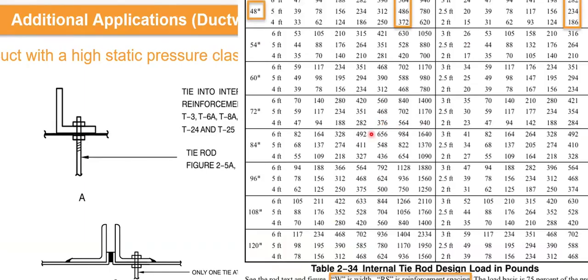This is a snippet that I included for a 48-inch wide duct. If you wanted to meet the 6-inch pressure rating, for a spacing of 4 feet for reinforcement, you need a tie rod that could withstand up to 372 pounds of force or load. If you wanted to increase that spacing to 6 feet, you need a much bigger tie rod that can withstand 564 pounds. Once you begin to have all of these every 6 feet, you're beginning to run into issues. I don't want to think of what you would have to do if you have a 120-inch wide duct. This is fairly common, as we deal with much, much larger or wider supply ductwork.